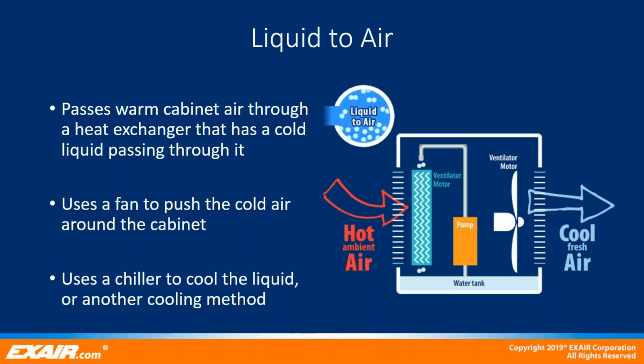Next, we'll talk about liquid to air. Liquid cooling is usually turned to when air to air doesn't have the required heat removal. Due to the cooled liquid, liquid to air can get below ambient temperature, unlike air to air. With liquid to air cabinet cooling, the air within the cabinet is cooled by flowing a cold liquid through a heat exchanger and distributing the air within the cabinet via the heat exchanger's fan. The cabinet cooler may receive the cold liquid from facility water or a chiller or another heat exchanger. Water inlet temp is assumed to be 68 degrees Fahrenheit in most cases, so some sort of secondary service is needed to provide that cold liquid.